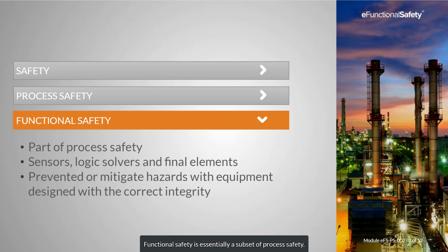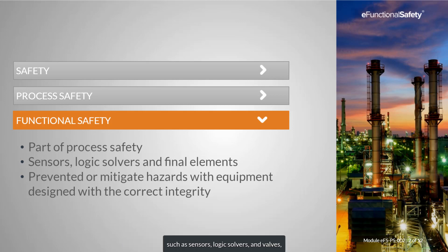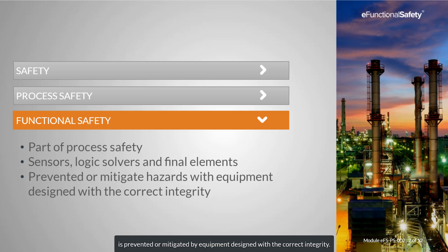Functional safety is essentially a subset of process safety. When hazards occur, the correct operation of automated equipment such as sensors, logic solvers and valves should bring the process to a safe state. Functional safety principles ensure that each hazard is prevented or mitigated by equipment designed with the correct integrity.